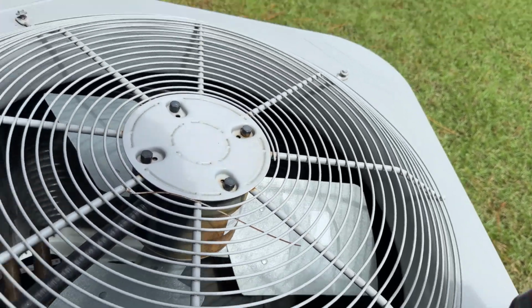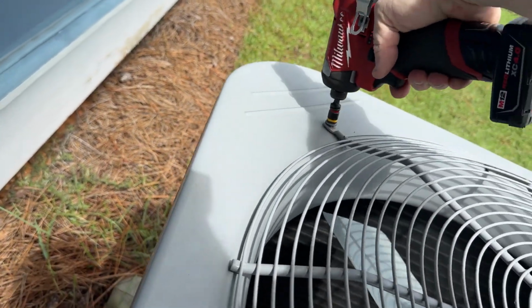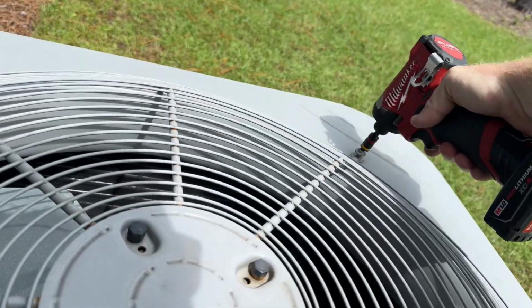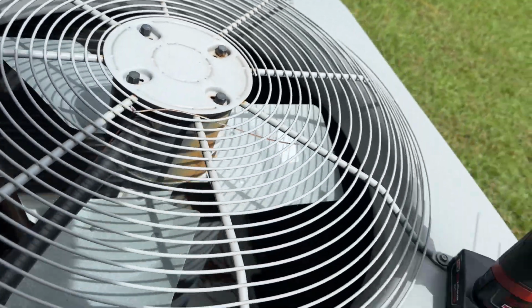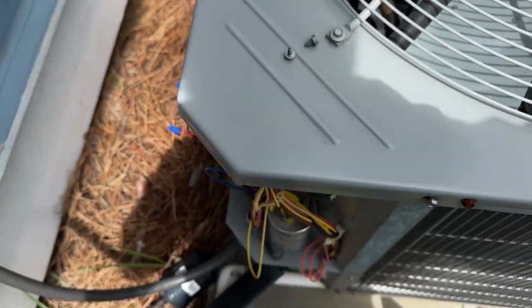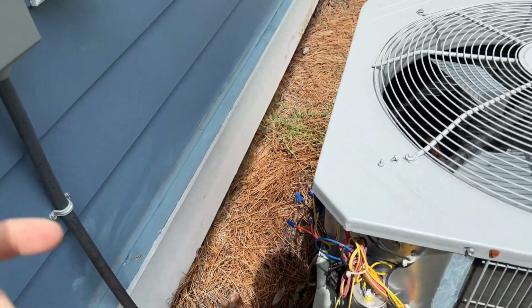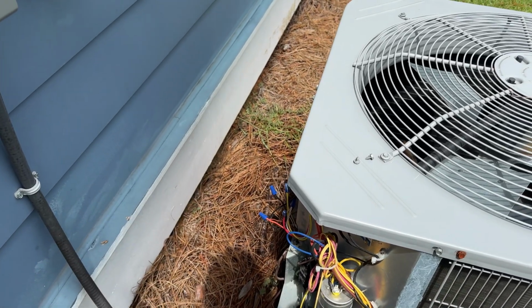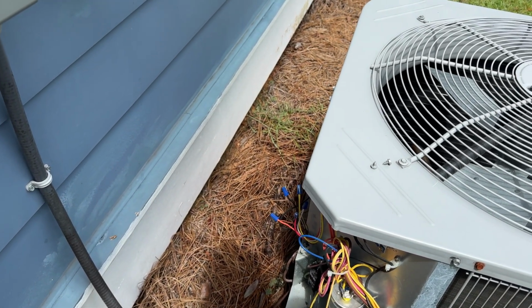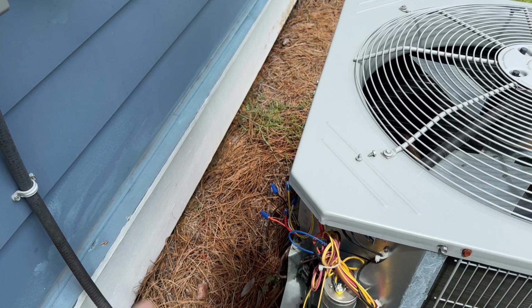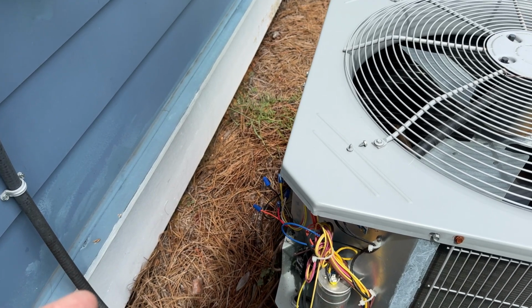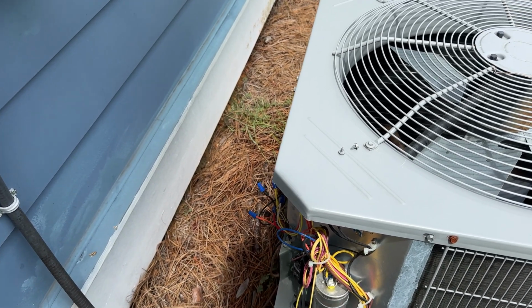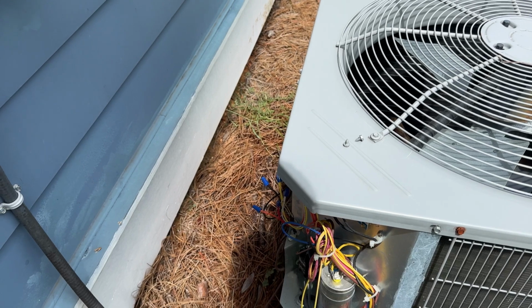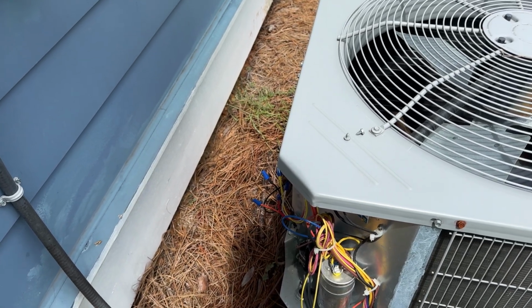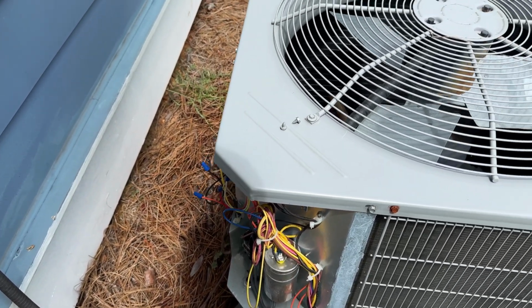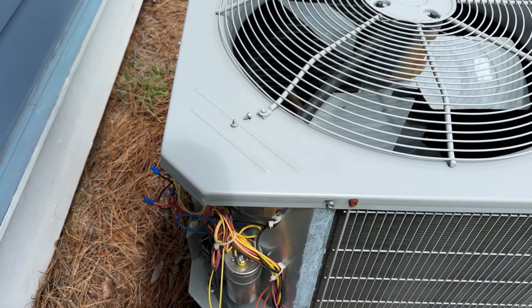They ran an extra wire to the emergency heat pin on the thermostat, the black wire, and connected it. So I disconnected that because it wasn't even needed. It was an extra wire going to heat strips when it wasn't needed, and now everything's working. Apparently it was bleeding through on stuff, but that was the bad wire. We're waiting for it to kick back on, putting the door back on.